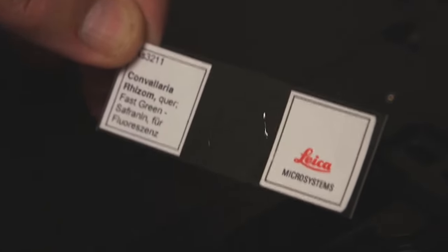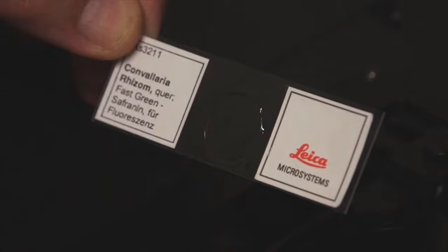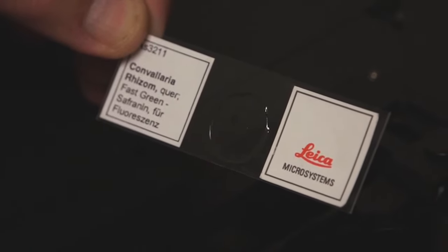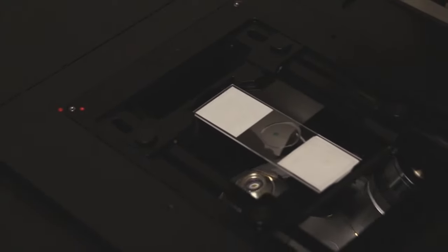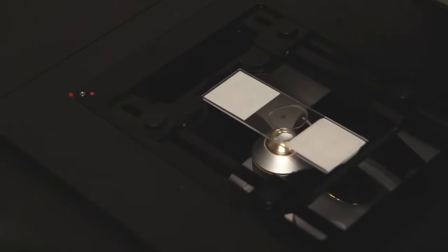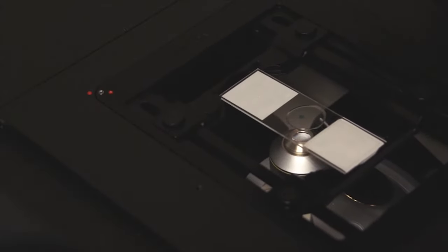If you are working with slides, you must flip your slide upside down because it is an inverted microscope. And so therefore, the part of the slide with the cover slip faces down onto the optic system. Make sure that you put your slide in that configuration or you will not see your image. Then you are free to dial the nose piece and bring the first objective, a 10x objective, into view.